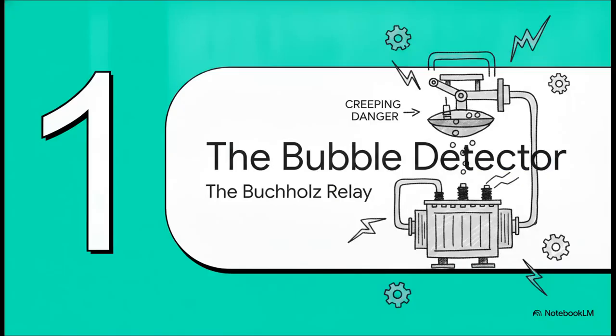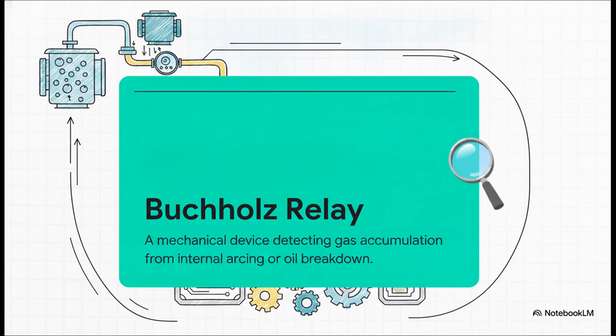Section 1. Meet the bubble detector, the Buchholz relay. Let's dive right into this and meet our mechanical hero. To catch that creeping, invisible danger, we rely on one of the most tried and true mechanical devices in the entire industry. Simply put, the Buchholz relay is essentially a bubble detector. If you look at the hardware, it sits right in the pipe, connecting the transformer's main tank to its overhead oil expansion tank, which we call the conservator.